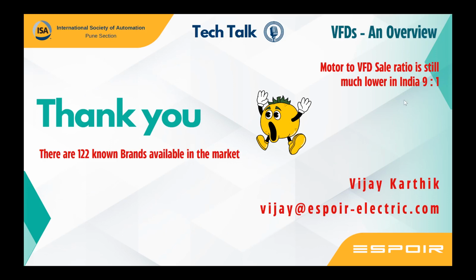Yes, when you use a VFD, you don't have to use a DOL starter, but you have to ask whether you need a VFD, whether you need speed control. Many questions are answered. Rajshekhar answered why altitude matters for a VFD. Air is rarer as we go up, so for example, a drive at high altitudes may require external cooling.